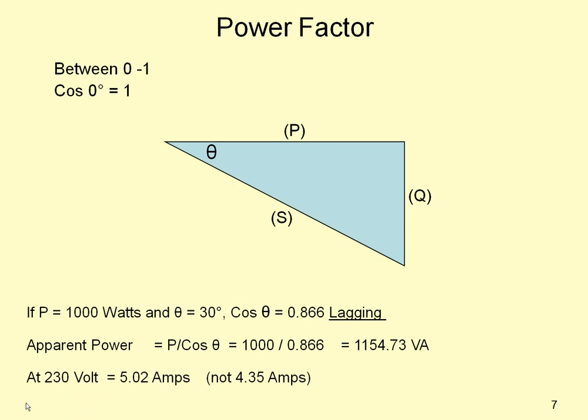At 230 volts, this will consume 5.02 amps, and not 4.35 amps, which it would do at unity power factor.